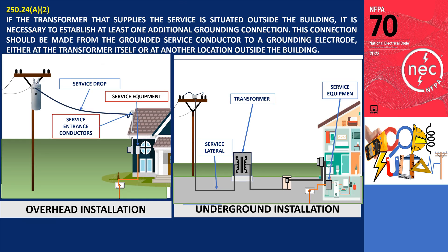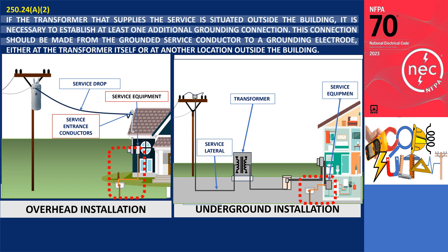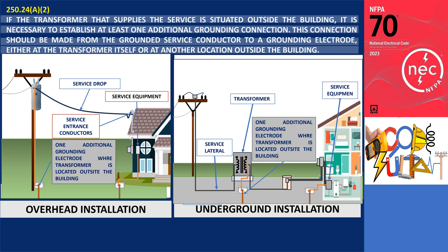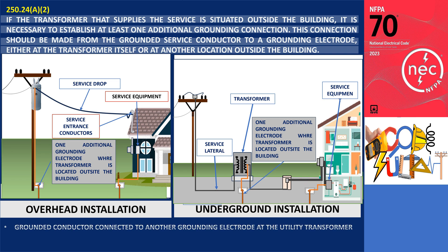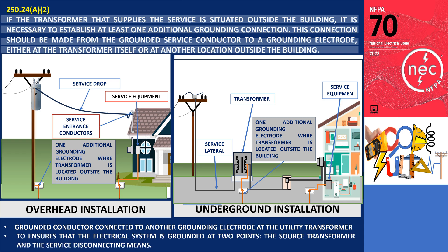In addition to the grounding connection for the grounded system conductor at the point of service entrance, according to 250.24(a)(2), if the transformer supplying the service is situated outside the building, it is necessary to establish at least one additional grounding connection. This connection should be made from the grounded service conductor to a grounding electrode, either at the transformer itself or at another location outside the building. This means a grounded service to a building must have the grounded conductor connected to a grounding electrode at the utility transformer, ensuring the electrical system is grounded at two points: the source transformer and the service disconnecting means. Service utilities typically adhere to NEC rules and ground their electrical systems, though they do so for a different reason — compliance with the National Electrical Safety Code.